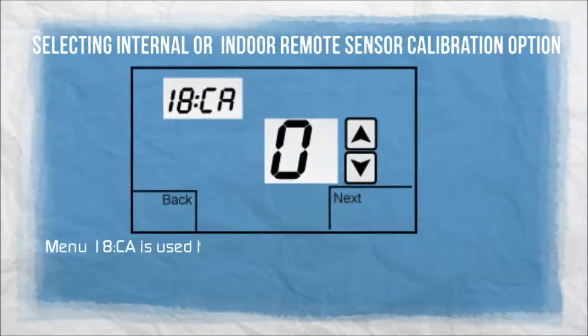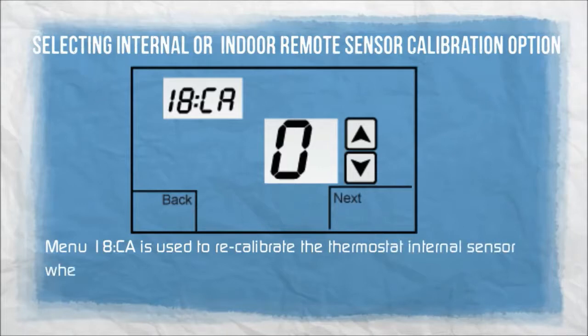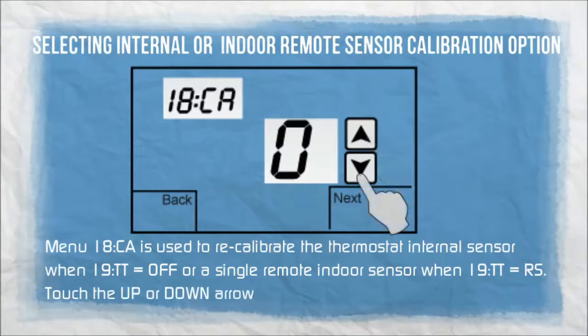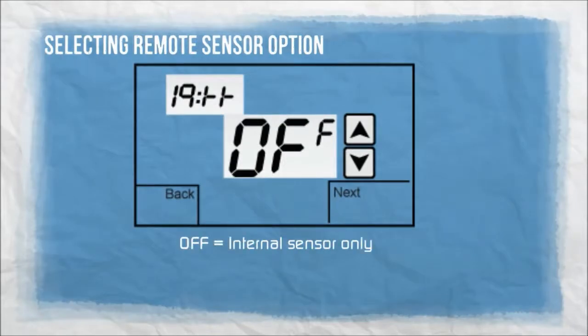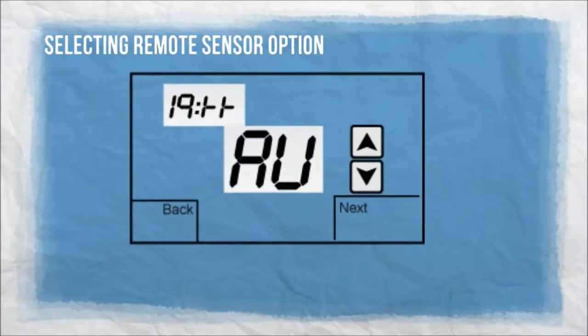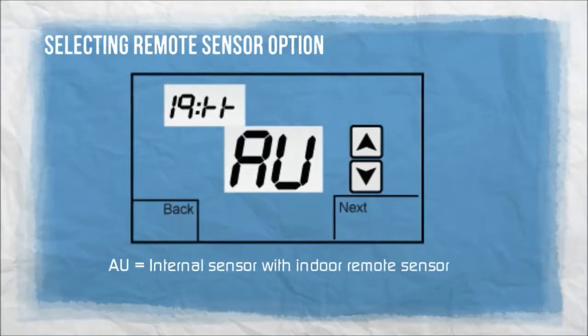Menu 18CA is used to recalibrate the thermostat internal sensor when 19TT equals OFF, or a single remote indoor sensor when 19TT equals RS. Touch the up or down arrows to adjust calibration. Off: internal sensor only. RS: indoor remote sensor only. AU: internal sensor with indoor remote sensor.